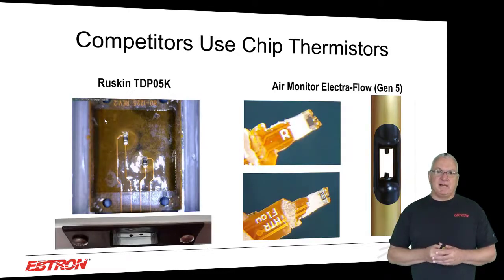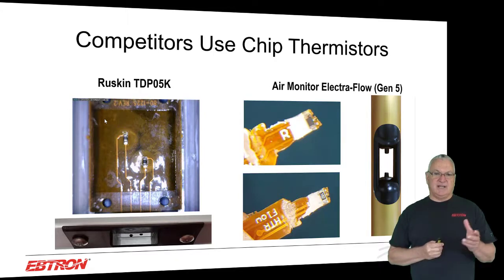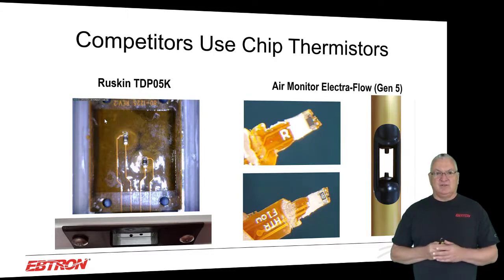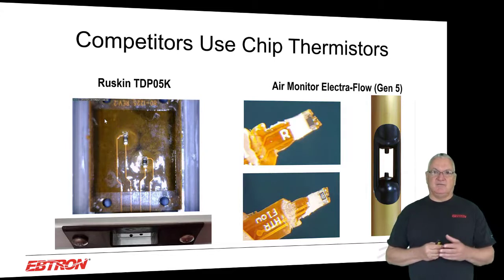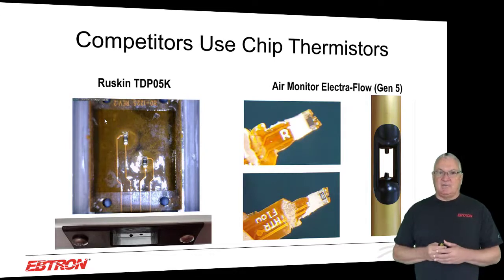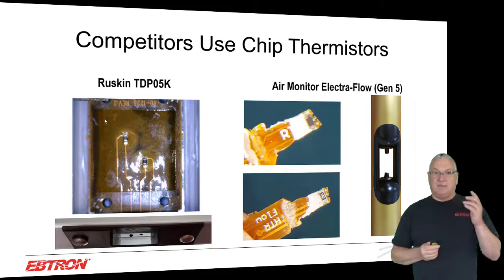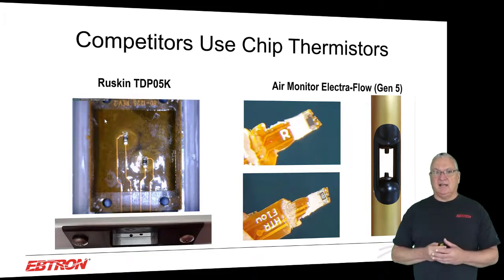When you look at our competitors, this is about the only thing I'm going to talk about with them. They use chip thermistors. It's an inexpensive part. It's a totally different way of doing things than we do. There you have the Ruskin part. You'll see those two chip thermistors that are basically put onto this flexible circuit that they use and then conformally coated. And then you have the air monitor unit, which also uses chip thermistors, and they don't actually self-heat their thermistor. They use a heating element. So when any of these folks come and say to you, well, it's just like an EBTRON, it clearly is not just like an EBTRON.